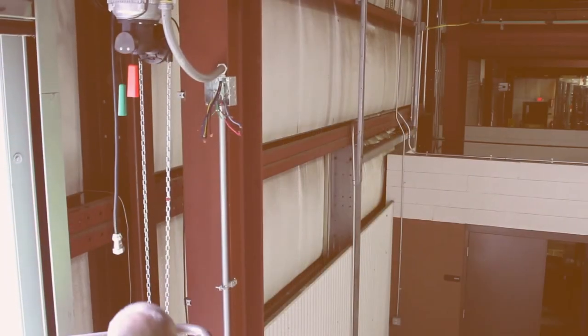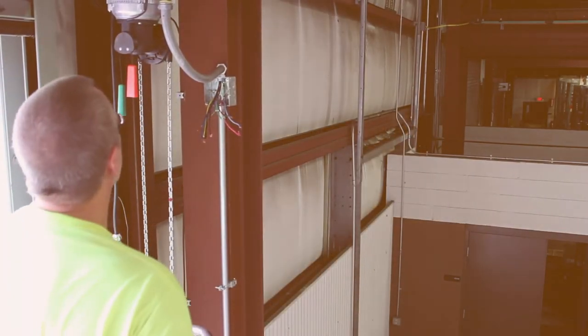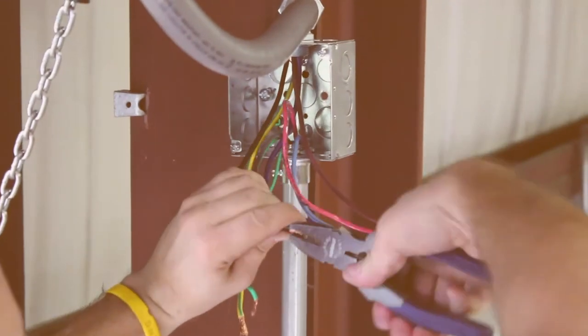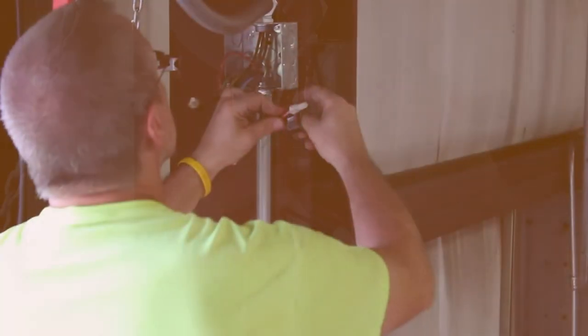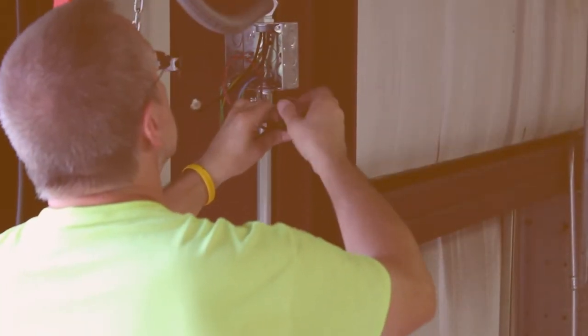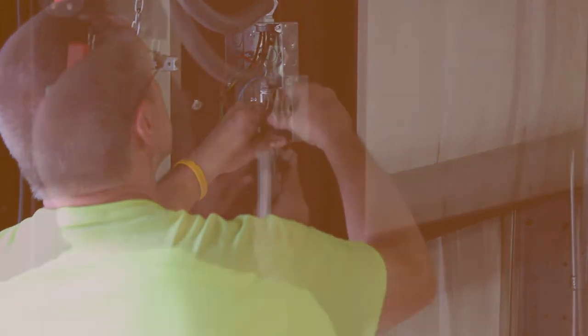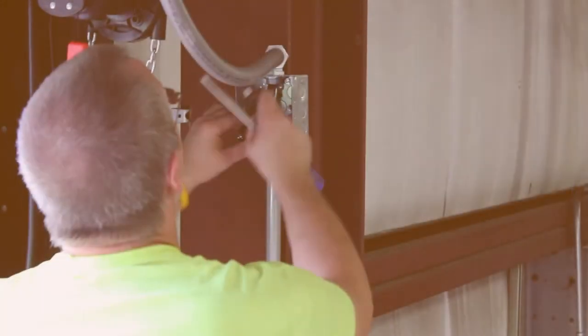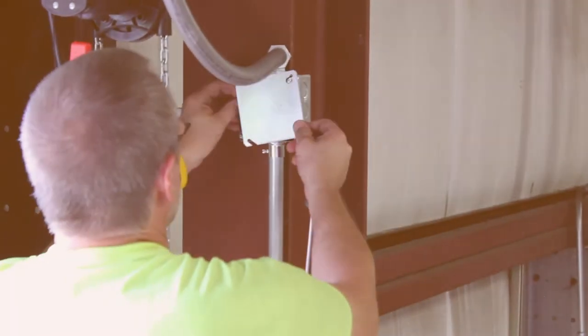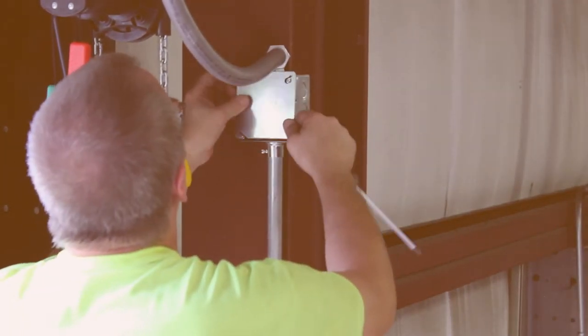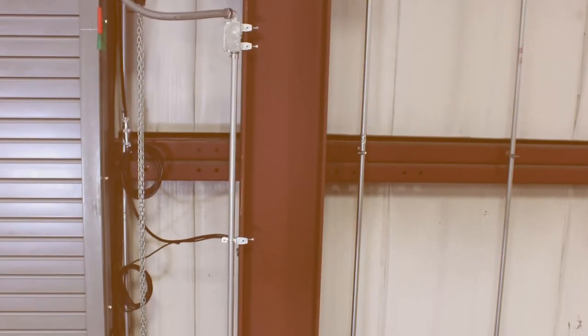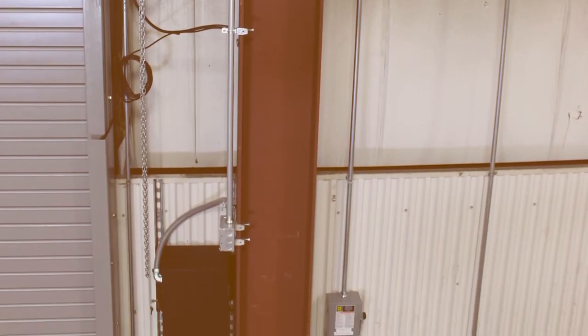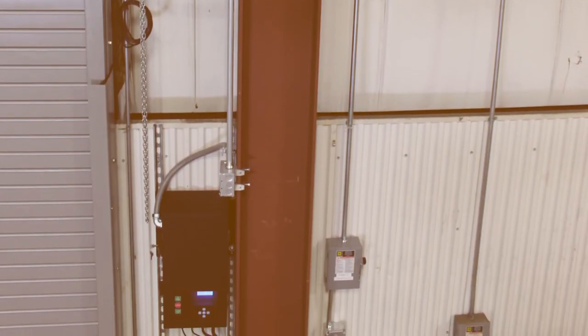Now we'll power the motor by connecting to the control panel. Match the wire colors black, brown, blue, yellow, green to the top junction box and connect with wire nuts or crimp style splices. Use rigid conduit between the junction boxes and then connect the Apex Smart Controller to the bottom junction box. Once again, refer to the diagram in the operation manual if necessary. Then, plug the brake power cable from the motor to the encoder cable from the panel.